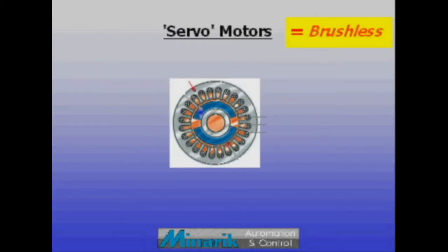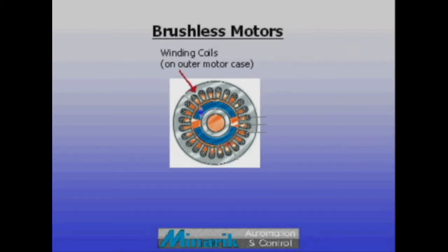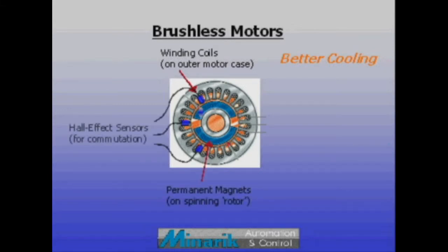Most often servo systems use brushless motors and drives, which combine the best features of AC and DC motors. Their windings are on the outer stator of the motor so they cool well. Their rotors contain only lightweight magnets and they don't use mechanical commutation, so brushless motors can accelerate fast.